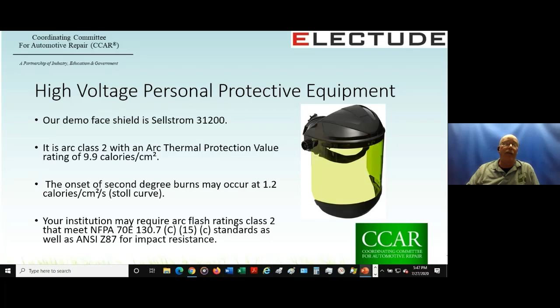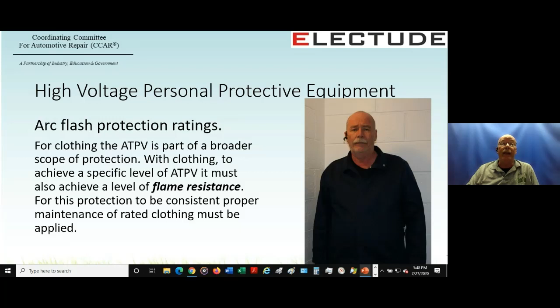thermal protection value. So when we're discussing rated clothing, like this simple jacket pictured here, it's important to realize that for clothing to be ATPV rated, it will inherently acquire a level of fire resistance, or better termed, flame resistance. Now, to maintain the minimum rating of this garment, it needs to be maintained or washed in a proper manner. At the same time, it's important to distinguish that while being arc rated makes an article fire resistant, being fire resistant doesn't necessarily make you arc rated.